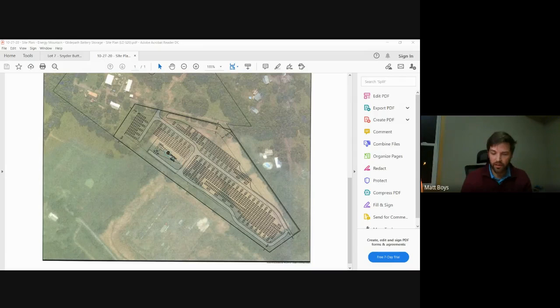That also means we look at locations, ideally, adjacent to existing electrical substations. That way we reduce the need for additional infrastructure, such as a standard 34 kV transmission line and poles, if this facility were not adjacent to a substation. Being adjacent to one means that with minimal additional poles we can connect right to that substation, where we pull energy off the grid and put it back on as required.